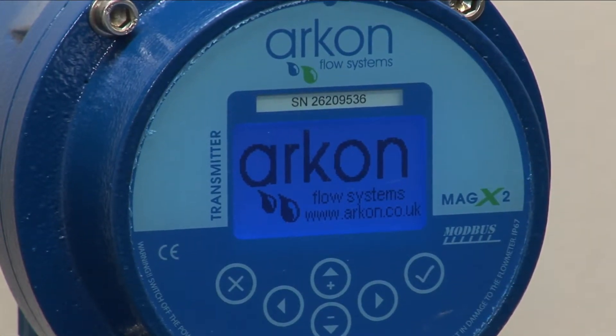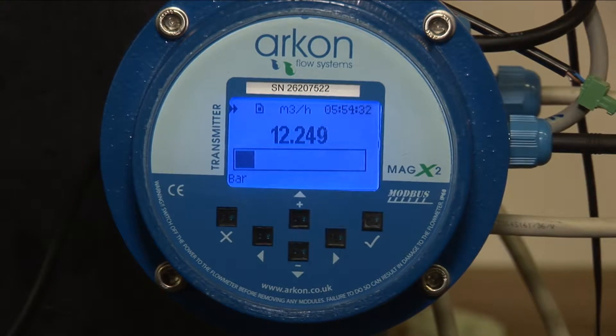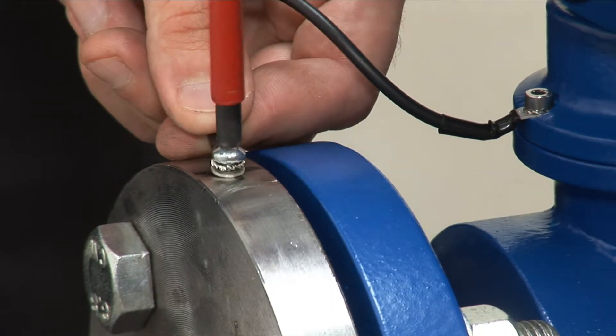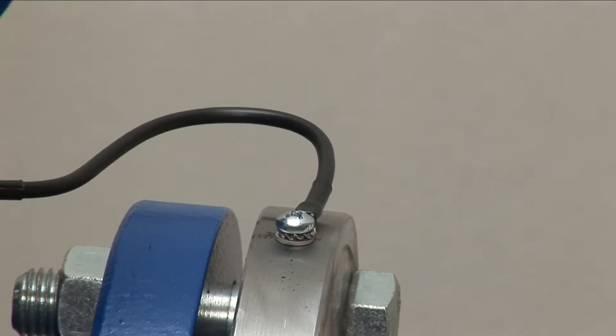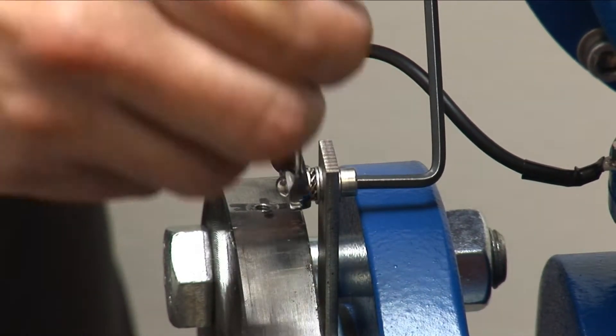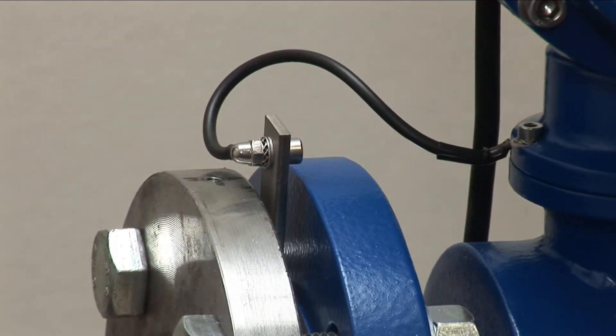Troubleshooting. In case your readings are unstable, here follows a list of the most frequent problems. Number 1: Insufficient or missing grounding. Sometimes installation companies forget to ground the meter or do not install earthing rings. Please note, each Arkon flow meter needs to be grounded.